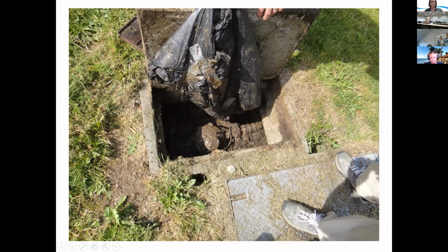And this is just a quick story on this one. A backflow event happened at a mill. They couldn't figure it out because they had RPBAs that were tested at the meters. They had two connections, and both had RPBAs. Everything should have been fine. They winterized their sprinkler system, and air was getting into the distribution system. Turns out they had another connection on the other side of the property to the distribution main that nobody knew about. Only one person did. So talk to people while you're out there and try to find things.